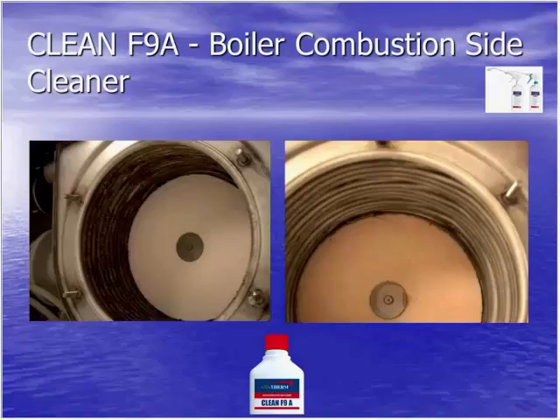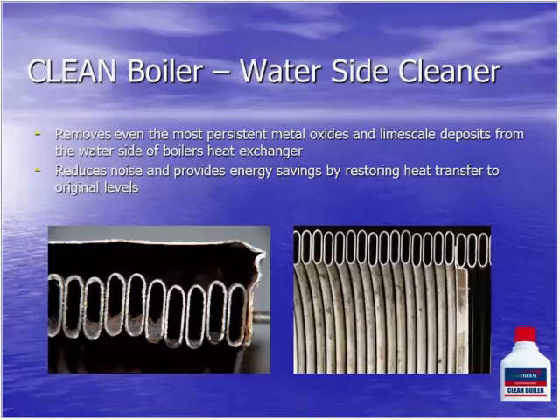And this is the wet side cleaner that we have specifically for boiler heat exchangers. It's a high potency or high dosage product, mixed at about a 10 to 20% dosage. It's meant for the heat exchanger and near boiler piping only. It removes even the most persistent metal oxides and limescale buildup from the water side of heat exchangers. It will help reduce the noise and provide energy savings, obviously by trying to restore the heat transfer to an initial level.